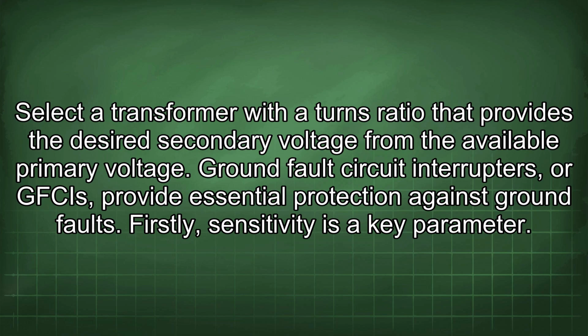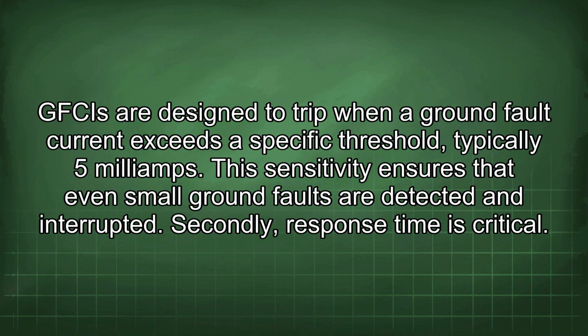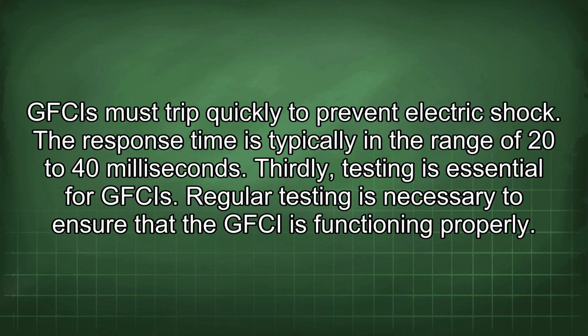Ground fault circuit interrupters, or GFCIs, provide essential protection against ground faults. Firstly, sensitivity is a key parameter. GFCIs are designed to trip when a ground fault current exceeds a specific threshold, typically 5 mA. This sensitivity ensures that even small ground faults are detected and interrupted. Secondly, response time is critical. GFCIs must trip quickly to prevent electric shock. The response time is typically in the range of 20 to 40 milliseconds.